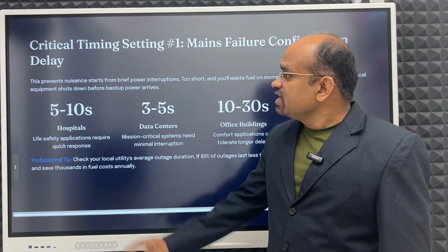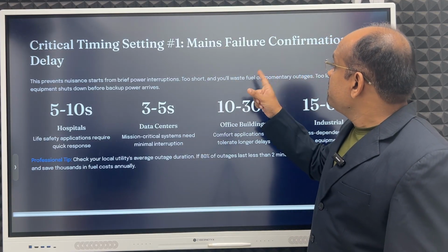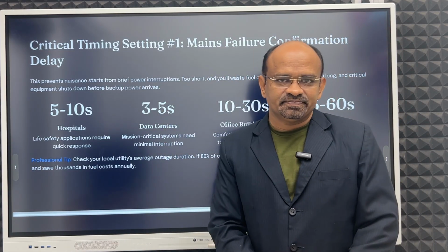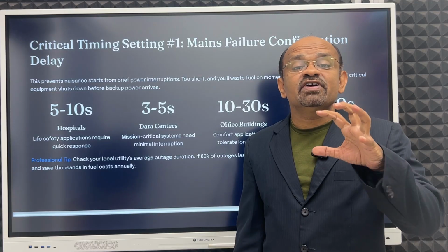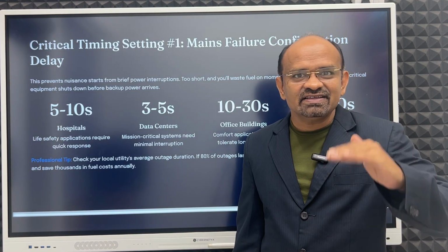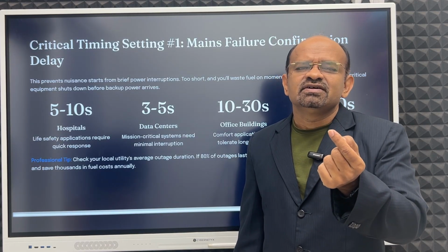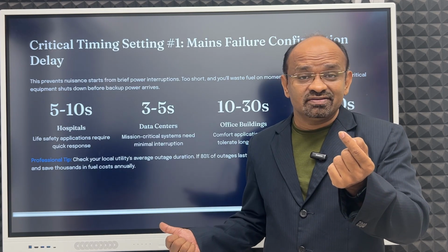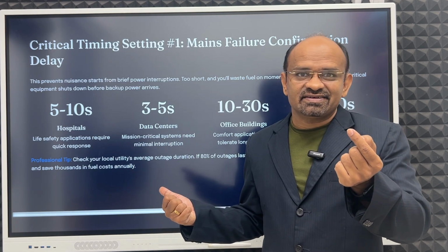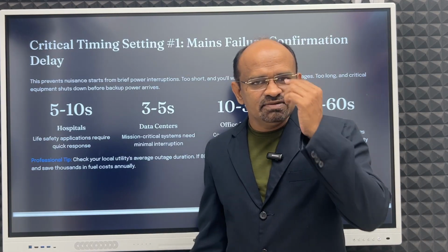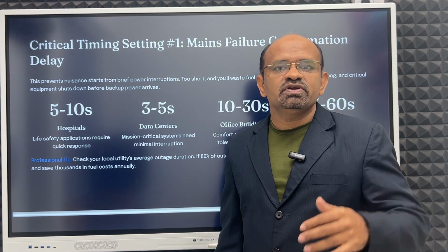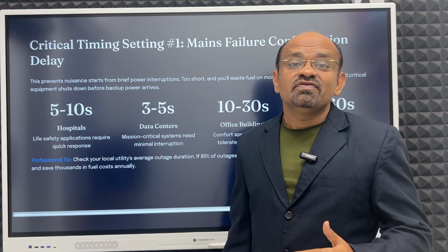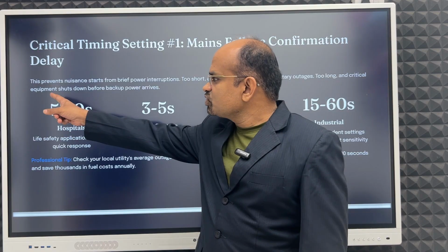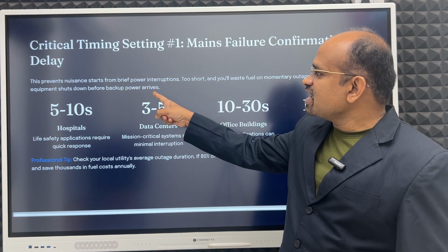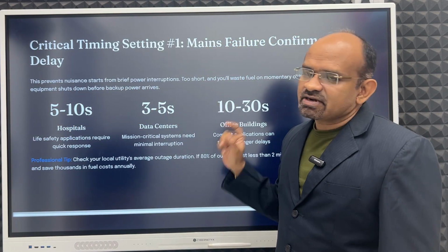Now, important thing, critical time setting: mains failure confirmation delay. Now, mains has failed, but a confirmation delay is required, right? Whether there is a real problem or a small spike, in that case, we should not switch on the diesel generator. Because it is in milliseconds, why should we switch on? It will be switched on, switched off. So without reason, this is called nuisance. Okay, so we don't want that. So this prevents nuisance starts from brief power interruptions.